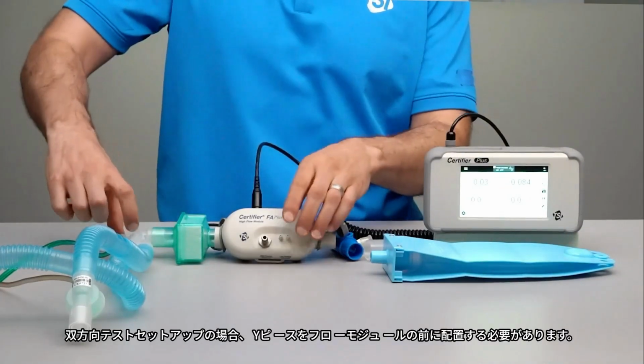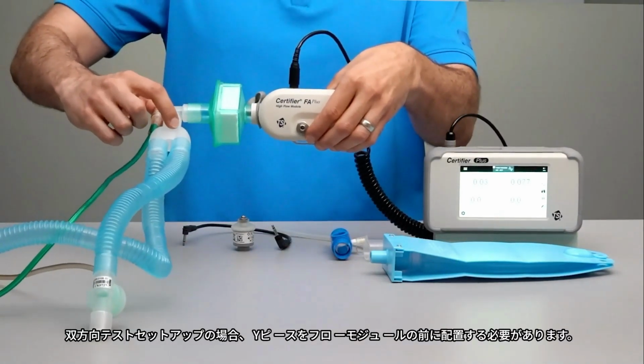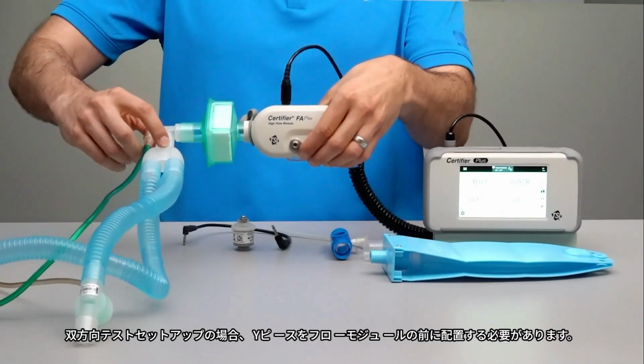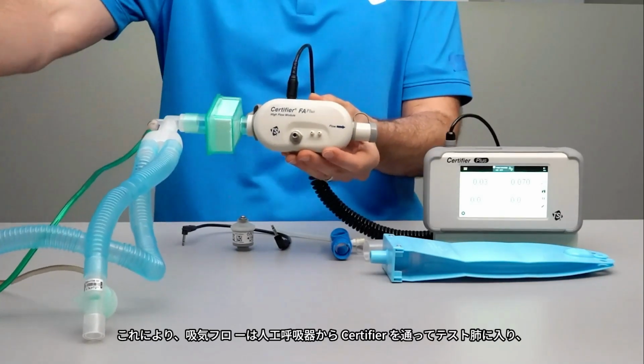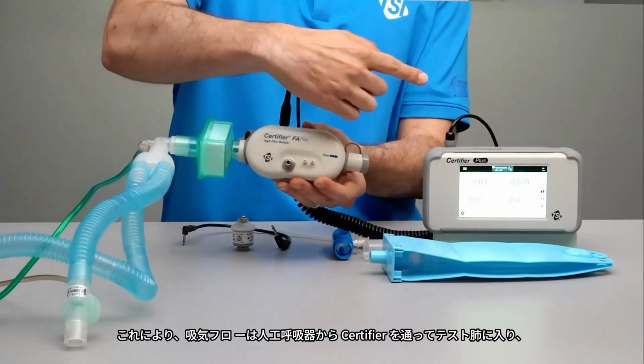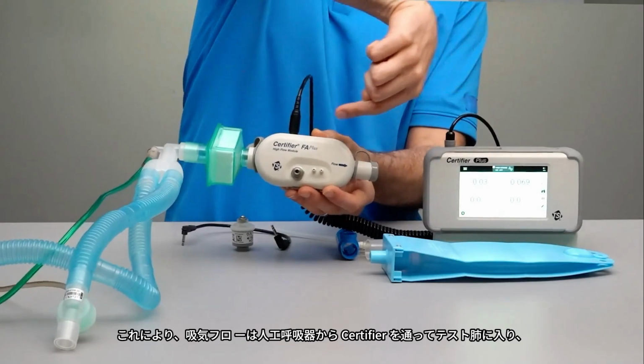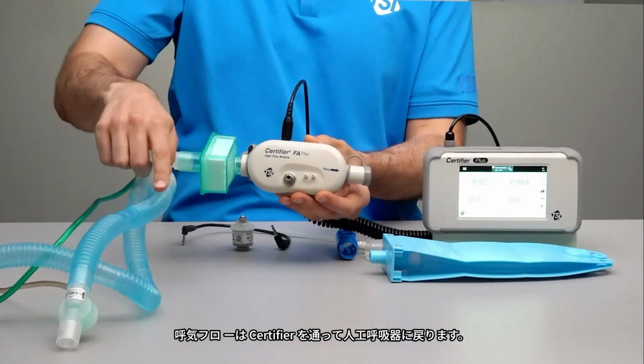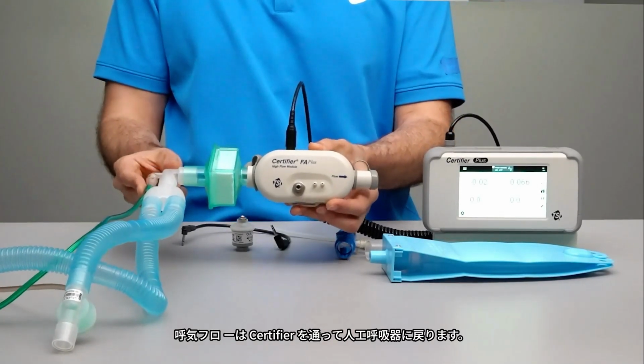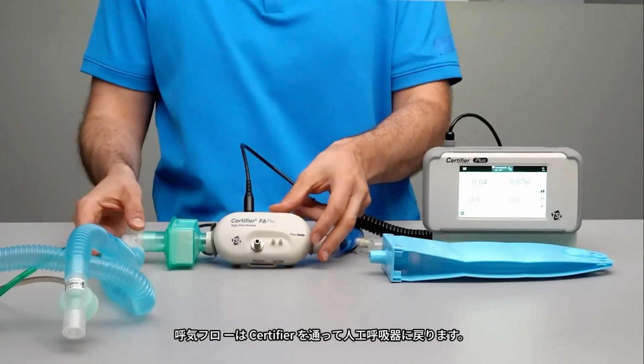For a bidirectional test setup, the Y fitting needs to be placed before the flow module so that the inspiratory flows come from the ventilator through the certifier into the test lung and then back through the certifier as expiratory flows, which then return to the ventilator.